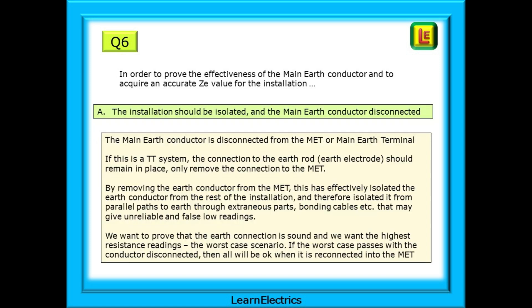The answer choice is A. The installation should be isolated and the main earth conductor disconnected from the MET or main earth terminal. If this is a TT system, the connection to the earth rod or earth electrode should remain in place, only remove the connection to the MET.